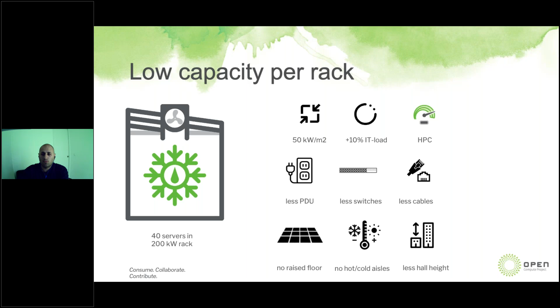Even if the temperature of the liquid is 50 degrees, the temperature of the chip is 60 degrees, which is much lower than in an air-cooled solution. Also, we resolve the problem with hotspots. Coolant is more efficient than air in transferring heat away from the IT. No condensation, short circuits, corrosion or static, clean environment, no dust, no fans, always high performance, excluding the possibility of zinc whiskers appearing, long-term reliability. Liquid creates a protective barrier between the environment and the IT equipment.